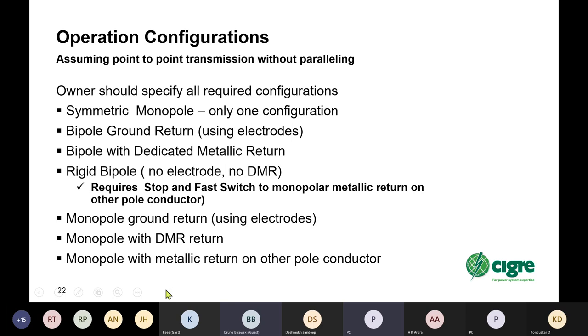And then, of course, there's monopole with ground return using electrodes, monopole with dedicated metallic return, monopolar with metallic return on the other pole, or another variant is monopole with both the DMR and the metallic return on the other pole to result in even lower losses.